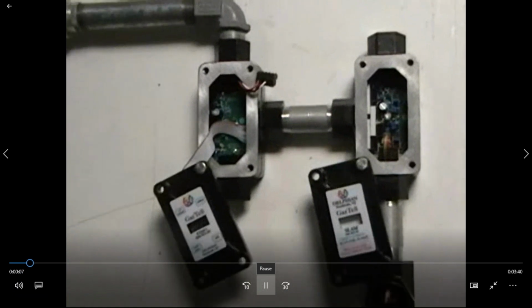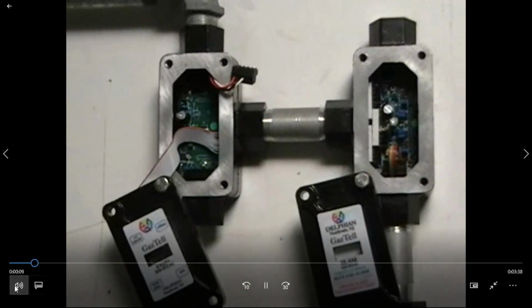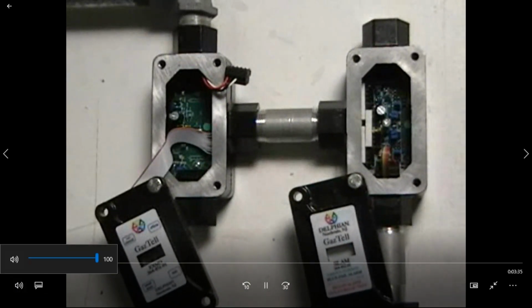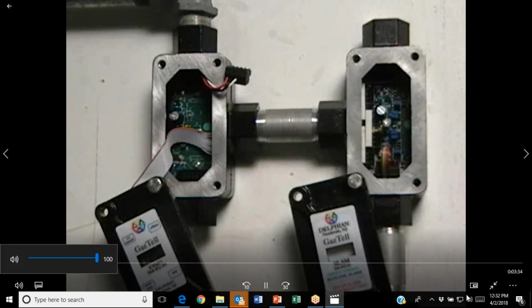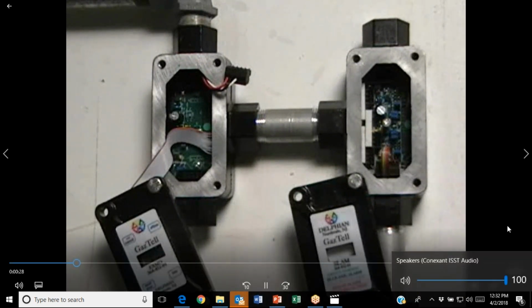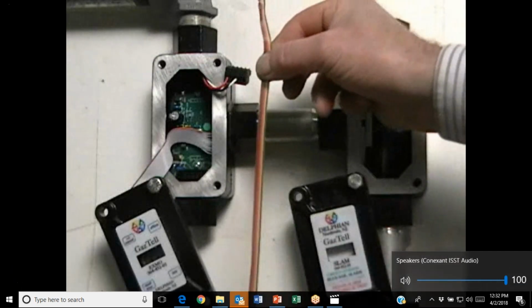In the installation, mount the detector and its optional modules if required onto 3/4 inch NPT conduit, making sure the conduit is properly secured. In many applications, the detector will be suspended from the conduit in open areas, such as ceilings. But if mounted against the wall, it is advisable to place a bend in the conduit to allow easy access to the detector when moving or when a foam splash guard might be used.